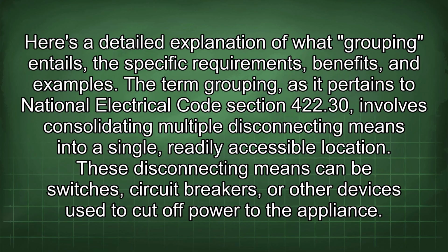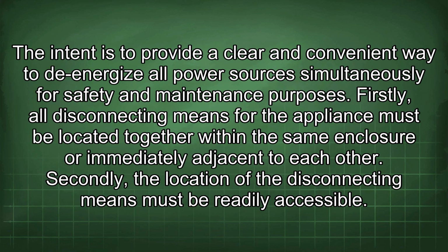The term grouping, as it pertains to National Electrical Code Section 422.30, involves consolidating multiple disconnecting means into a single, readily accessible location. These disconnecting means can be switches, circuit breakers, or other devices used to cut off power to the appliance. The intent is to provide a clear and convenient way to de-energize all power sources simultaneously for safety and maintenance purposes.